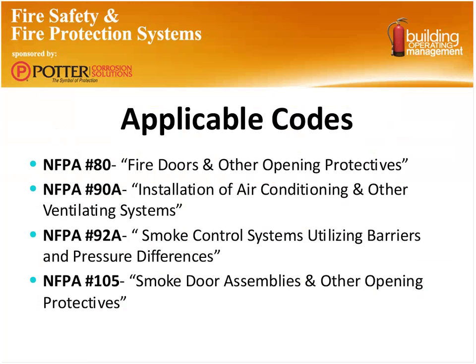Fire and smoke damper testing and maintenance is a critical piece in some occupancies, and the occupancies that we typically see this enforced most regularly in are your hospitals and other care facilities. The relevant codes that we deal with in these types of testing and maintenance would be NFPA 80 for your fire doors, NFPA 90A for air conditioning installations and other ventilating systems, NFPA 92A, smoke control systems, and NFPA 105, which is smoke door assemblies and other opening protectives.